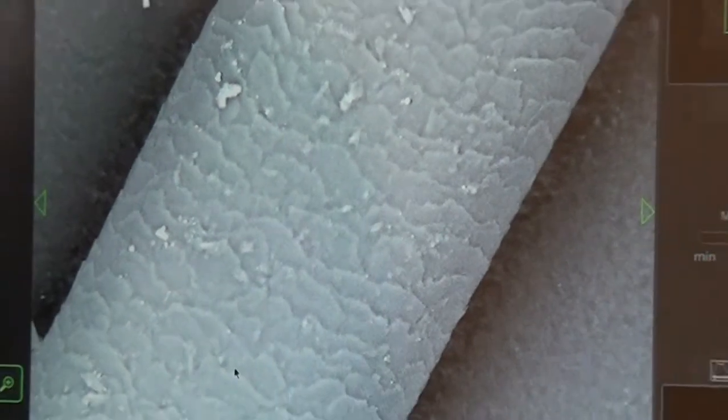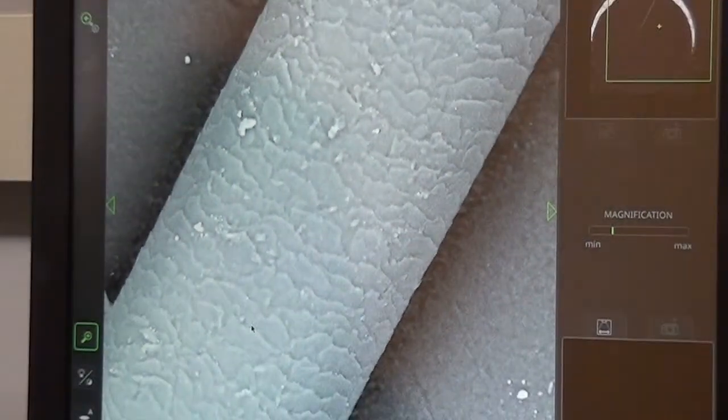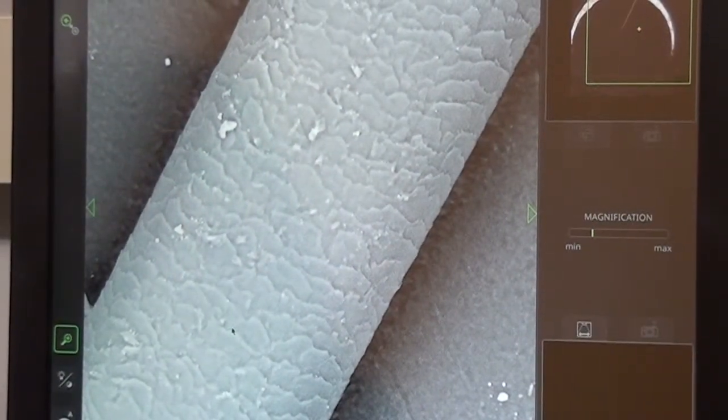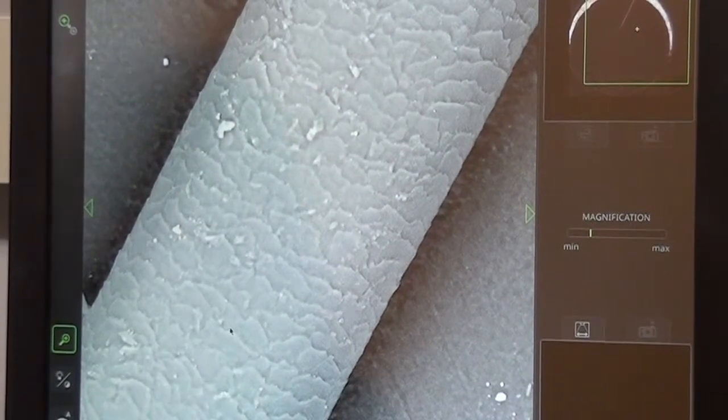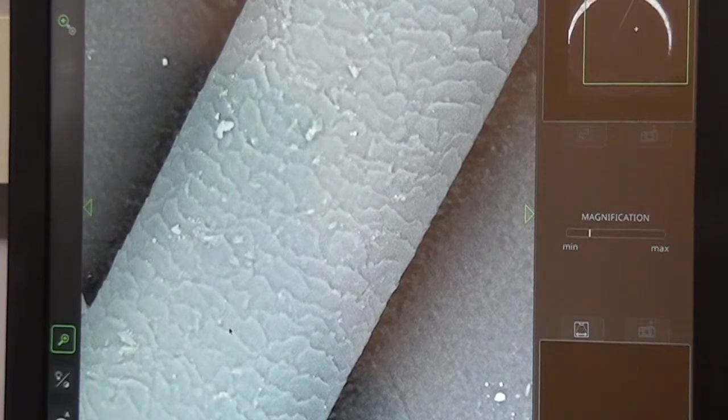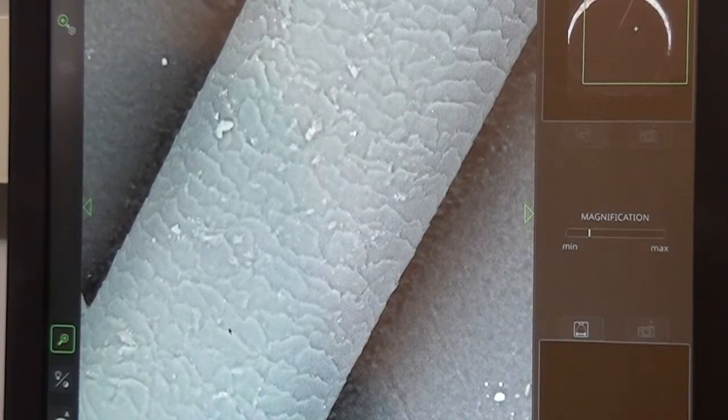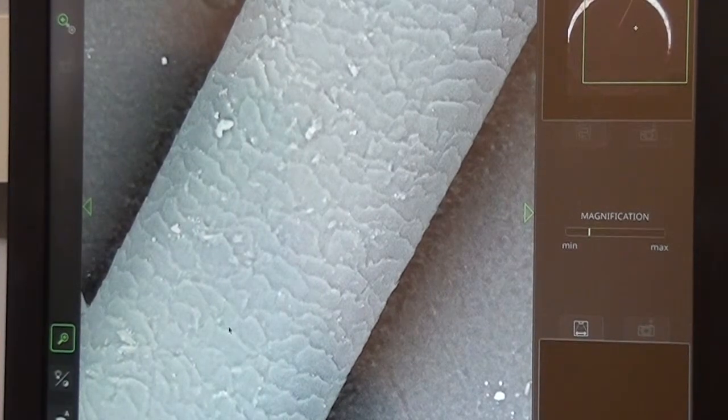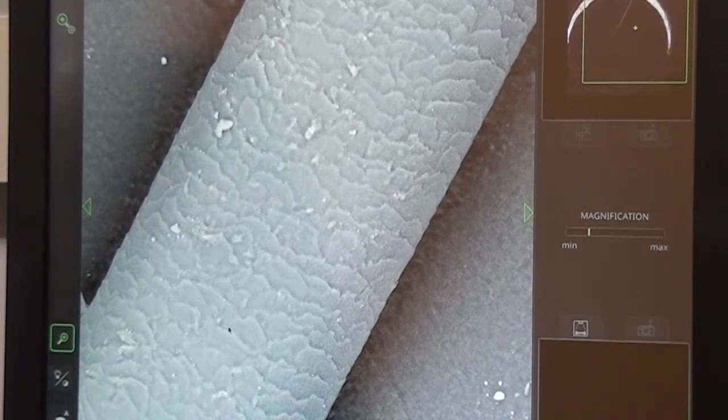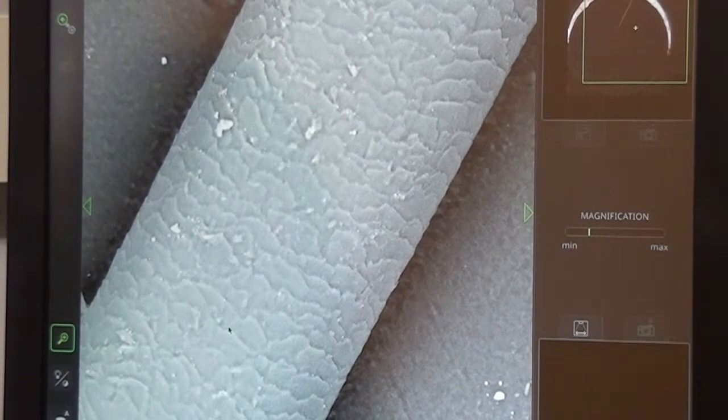Now on this sample in particular, because hair is an insulator, charging is going to occur really quickly. This is where a pool of electrons builds up on your sample because it's not conductive and there's nowhere for it to go. There's no path for it to flow off of.